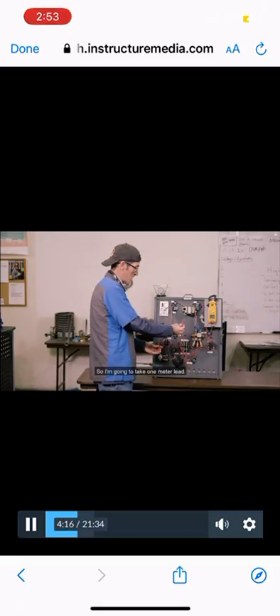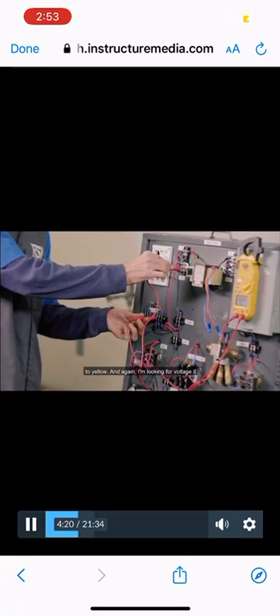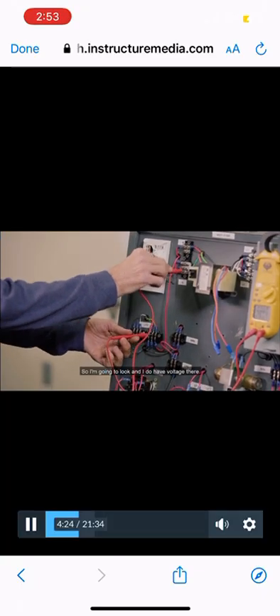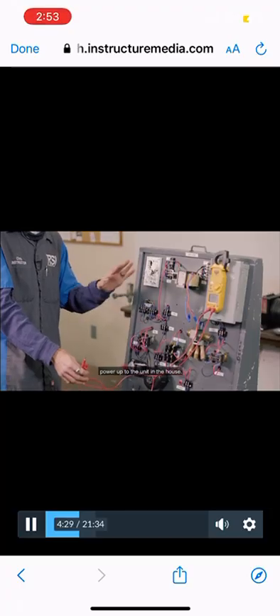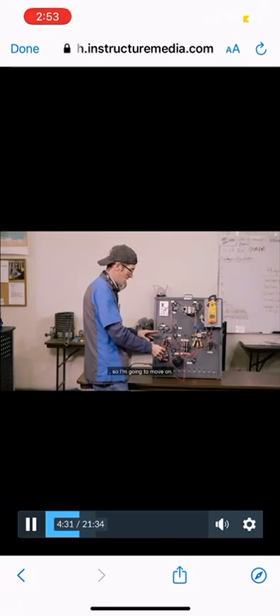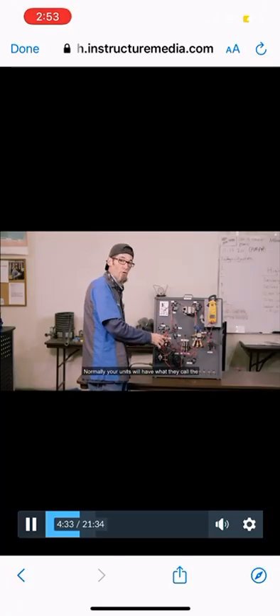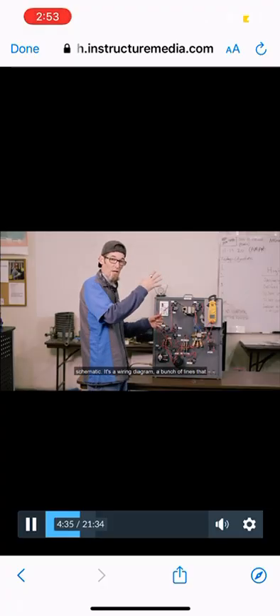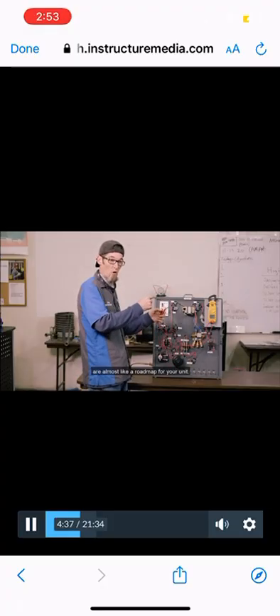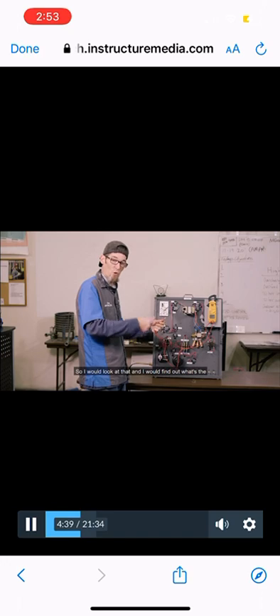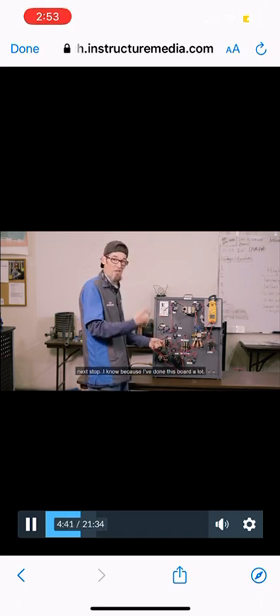So I'm going to take one meter lead, put it on common here, and go to yellow. Again, I'm looking for voltage if everything's working correctly. I do have voltage there. So that confirms to me that the thermostat is sending power up to the unit in the house. Okay, so I'm going to move on. Normally your units will have what they call a schematic. It's a wiring diagram, a bunch of lines that are almost like a road map for your unit. So I would look at that and find out what's the next stop.